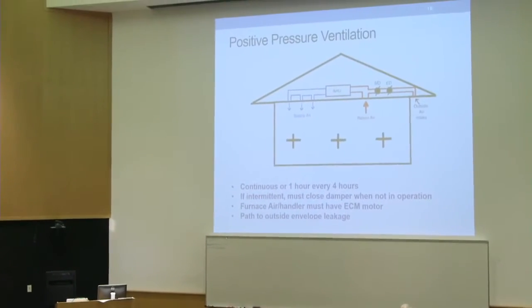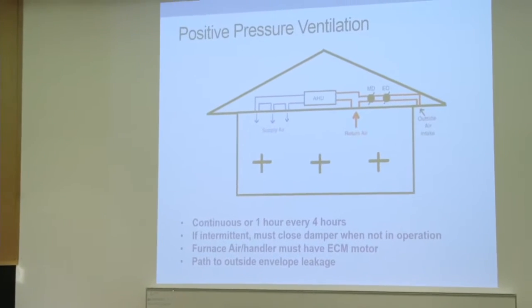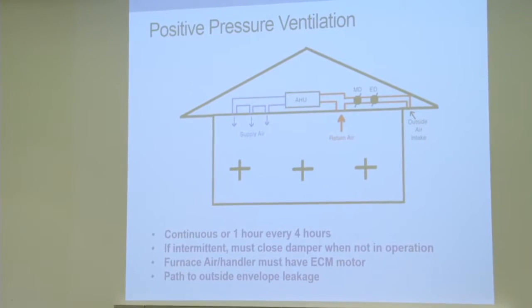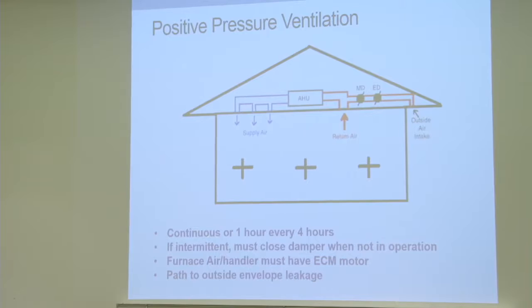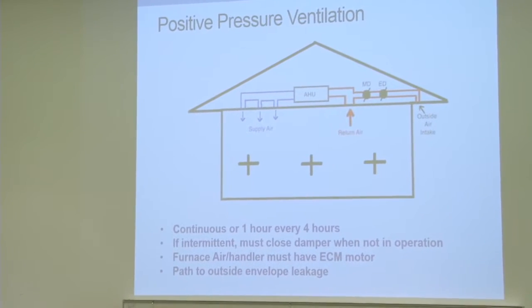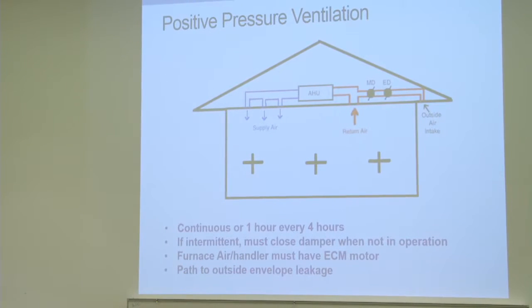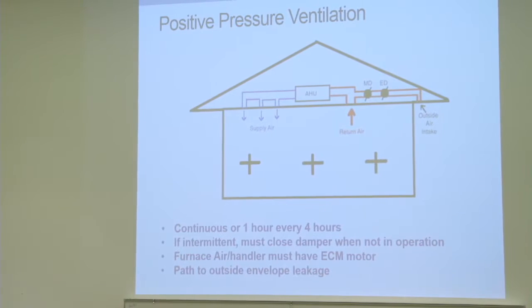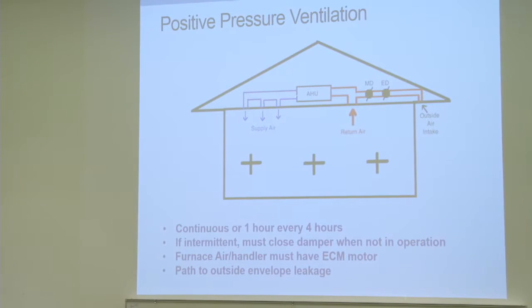So our positive pressure, we've really touched on most of this, but continuous or 1 hour every 4 hours. If intermittent, we have to make sure we close when it's not in operation. That has to have an ECM motor in it. This is going to cost you money.